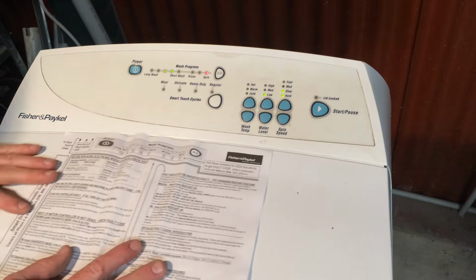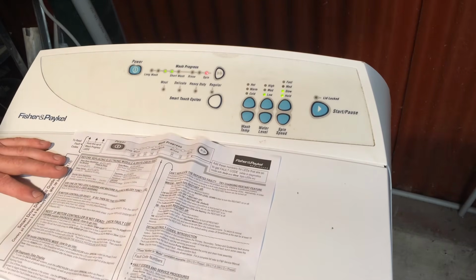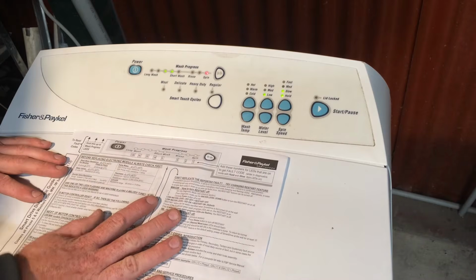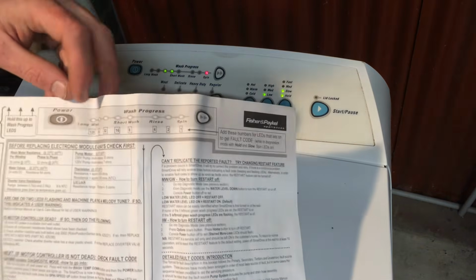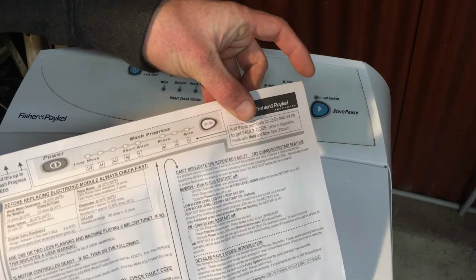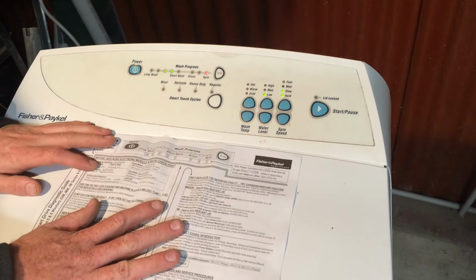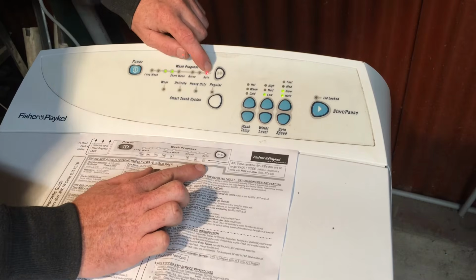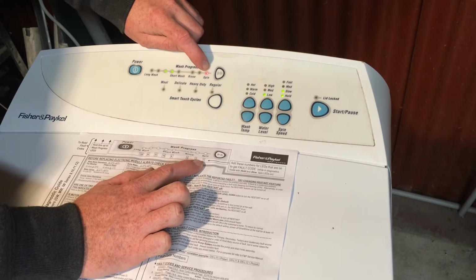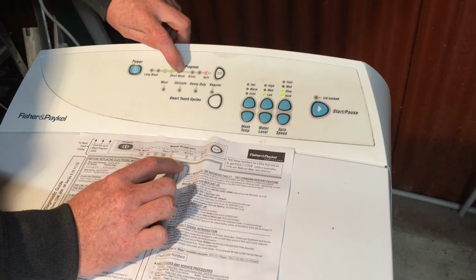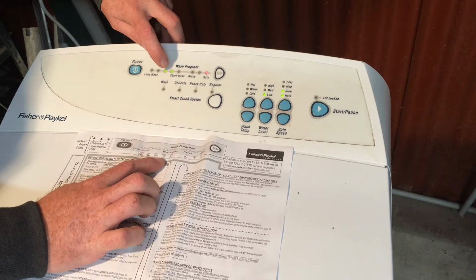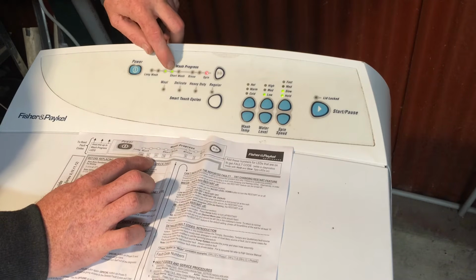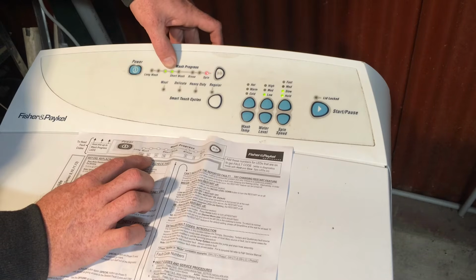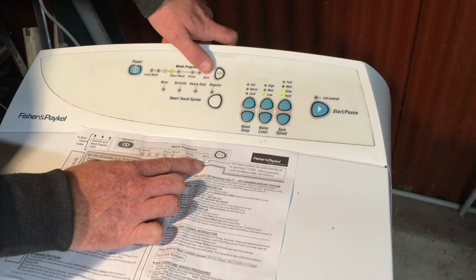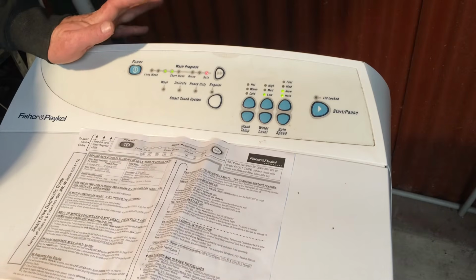Or you might find in any control boards, they have this little sheet here. And you'll find different sheets floating around on the internet. Basically, along the top here, it tells you what the value of each light is, so that we can do it that way. So the first light on the right, going from right to left, is worth a 1. That one's worth 2, 4, 8. We have 16 and 32. So if we add 32, 16 and 1, 32 and 16 is 48, and 1 is 49. So fault code 49 in the last 8 cycles.